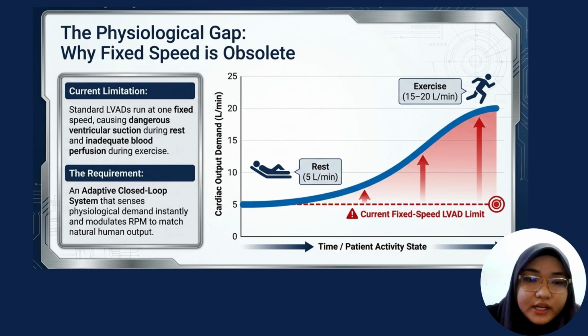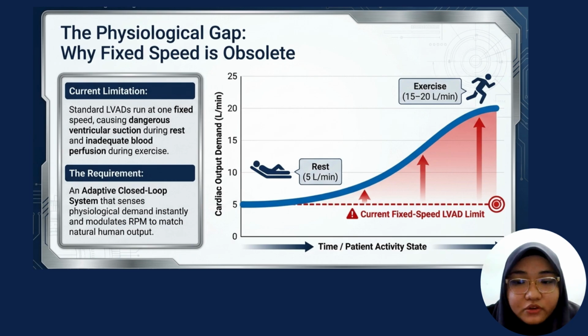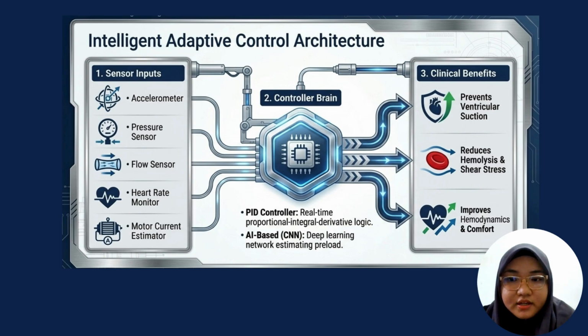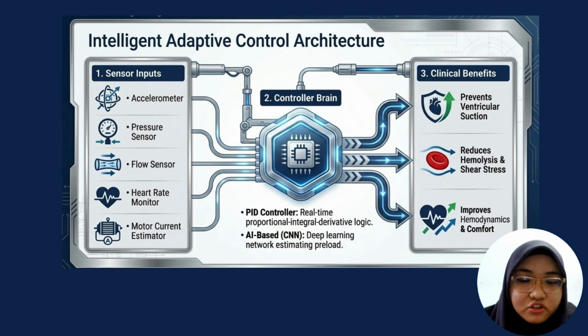Therefore, modern LVAD systems require an adaptive physiological control mechanism that can continuously regulate the pump performance according to the patient's real-time condition. So this creates the need for an intelligent closed-loop control system. Now, we're going to the adaptive control architecture for the AeroHeart maglev LVAD. The main objective of the system is to automatically adjust pump speed based on the patient's physiological demand, allowing the LVAD to behave more like a natural heart.